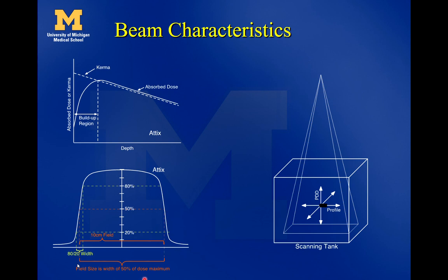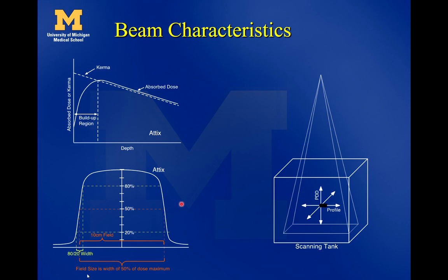Another important characteristic is field size, defined as the width at 50% of the maximum dose. Starting at 100% on central axis, the field size is determined by how wide the beam is where you're getting half the dose as you go from inside to outside the beam. The linac manufacturers make it so that the 50% isodose width matches what the light field shows anyway.